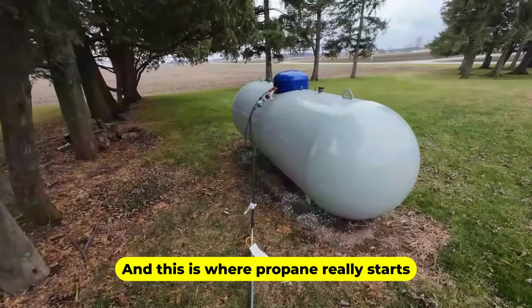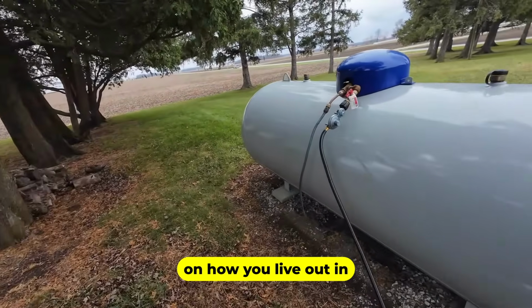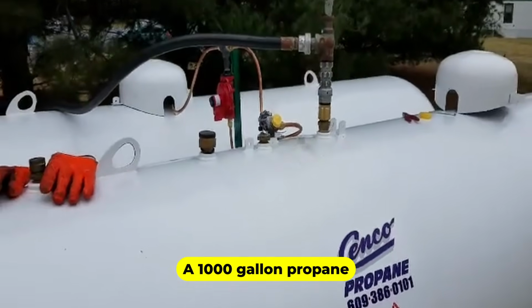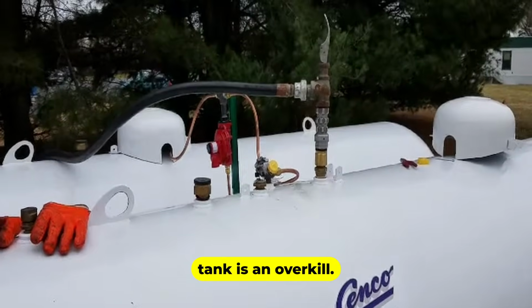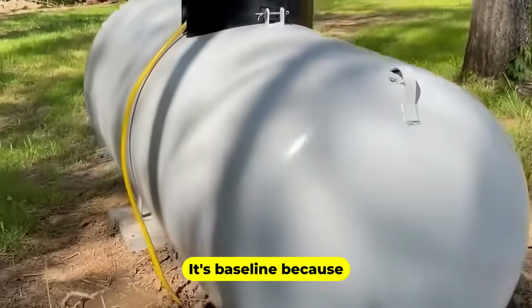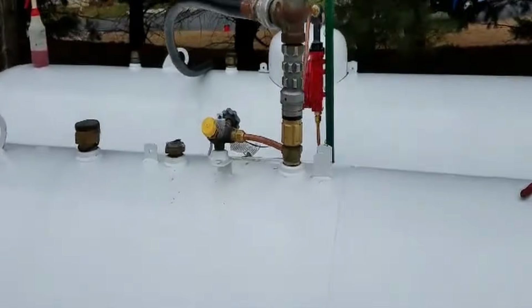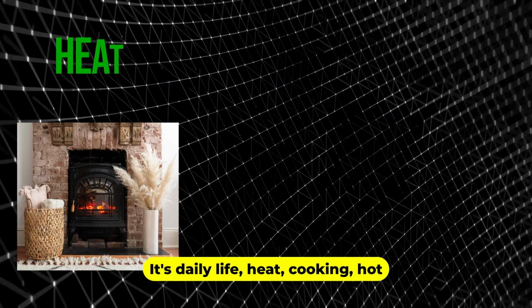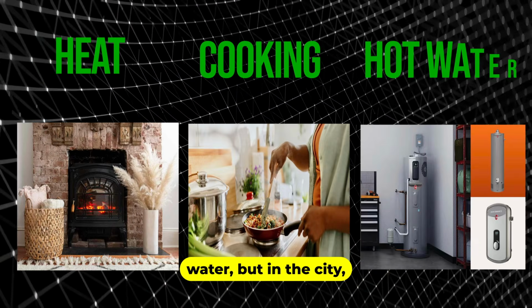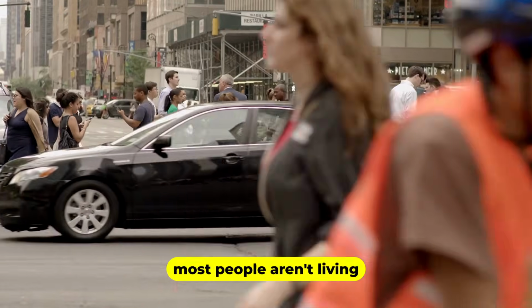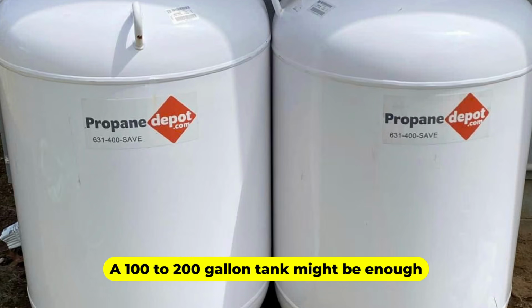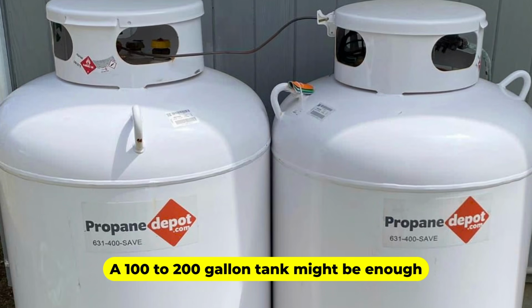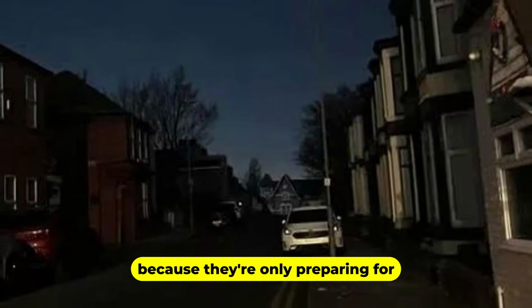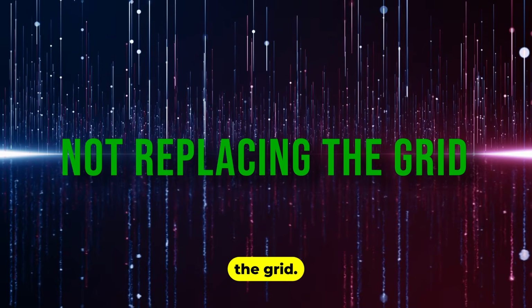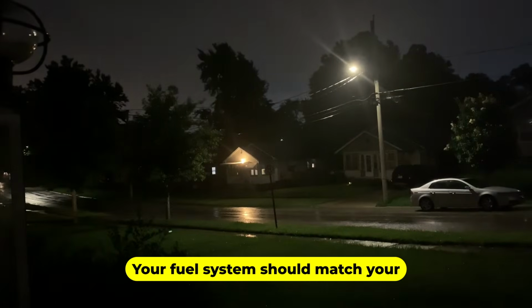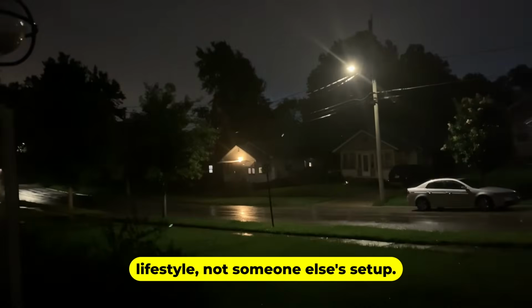And this is where propane really starts to make sense depending on how you live. Out in the country, a 1,000-gallon propane tank is no overkill. It's baseline, because that fuel isn't just backup, it's daily life: heat, cooking, hot water. But in the city, most people aren't living that way. A 100 to 200-gallon tank might be enough because they're only preparing for outages, not replacing the grid. Your fuel system should match your lifestyle, not someone else's setup.